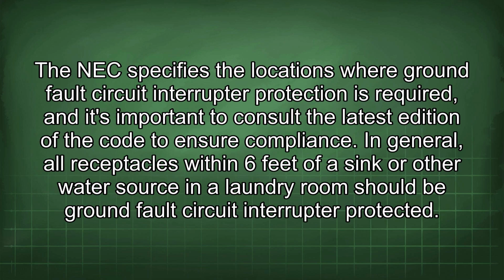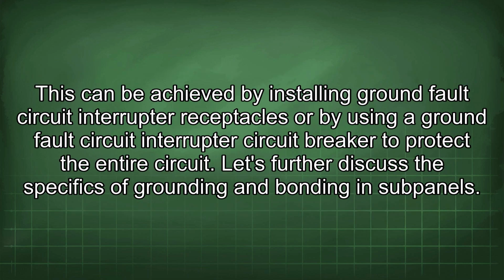The NEC specifies the locations where ground fault circuit interrupter protection is required, and it's important to consult the latest edition of the code to ensure compliance. In general, all receptacles within 6 feet of a sink or other water source in a laundry room should be ground fault circuit interrupter protected. This can be achieved by installing ground fault circuit interrupter receptacles or by using a ground fault circuit interrupter circuit breaker to protect the entire circuit.